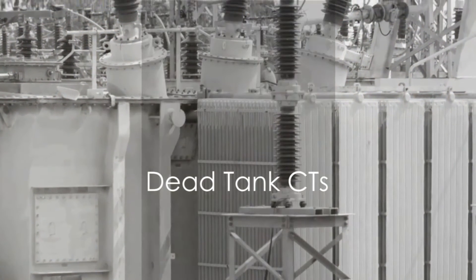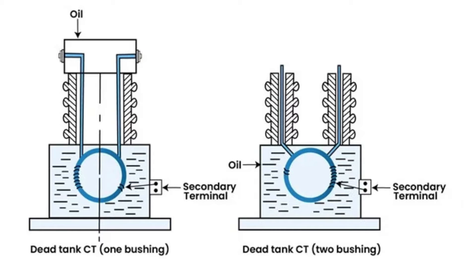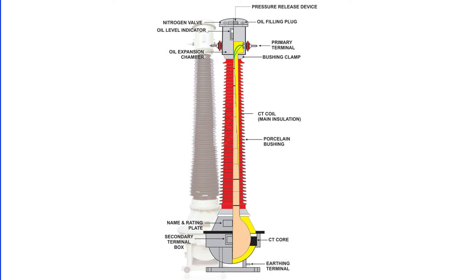Now let's consider dead tank CTs. In this case, the core and secondary winding are housed in the bottom tank, which is earthed or dead. The primary winding is brought down to the bottom tank and insulated from the earthed tank and cores. This design, however, presents a challenge, as it's difficult to apply the predefined insulation over the primary because it needs to pass through the wound cores.